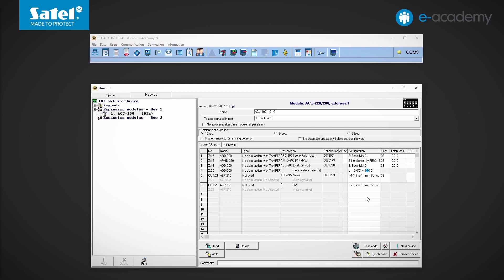What does the tolerance value mean? It indicates when the end of the violation will be reported. In the case of a low threshold, we add the value entered in the tolerance field to the threshold value. In the case of a high threshold, we subtract it from the threshold value. It is best to use an example to clarify this.